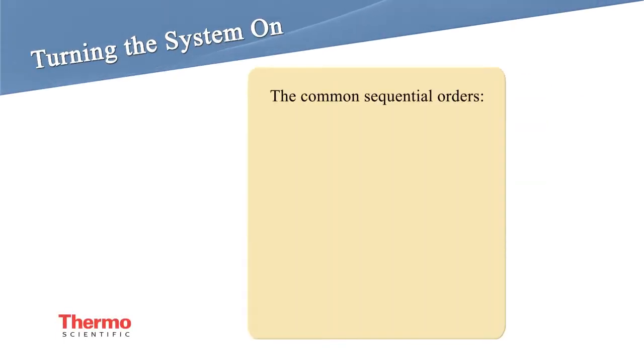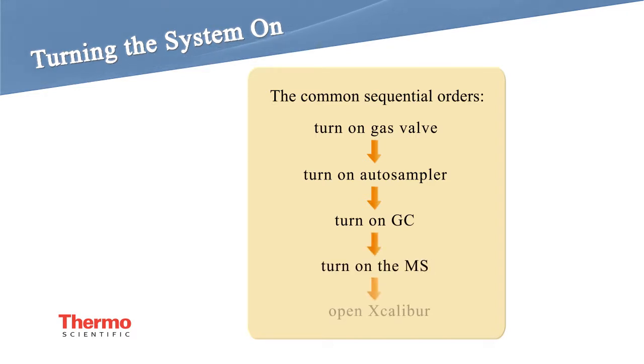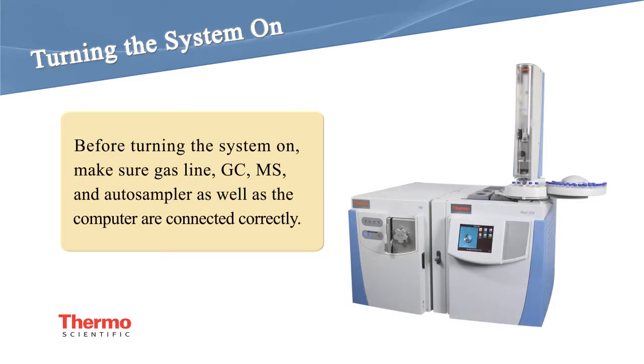Follow these steps for turning the system on: first turn on the gases, then turn on the autosampler, next turn on the GC and the mass spectrometer, and finally turn on the computer. Before turning on your system, please make sure...